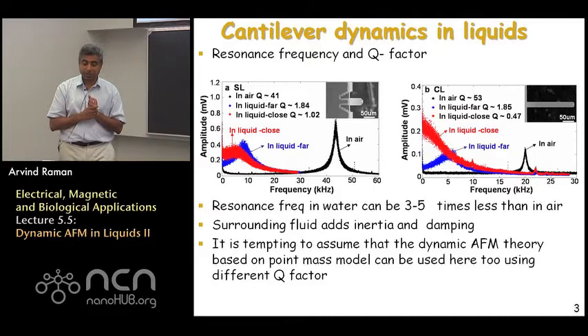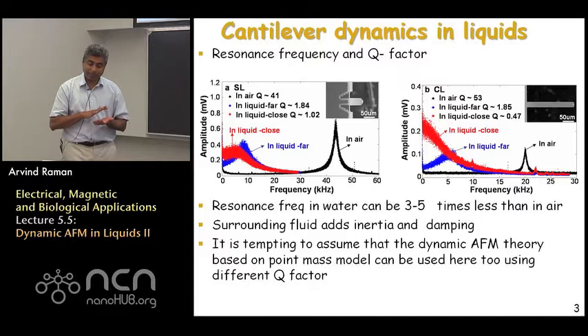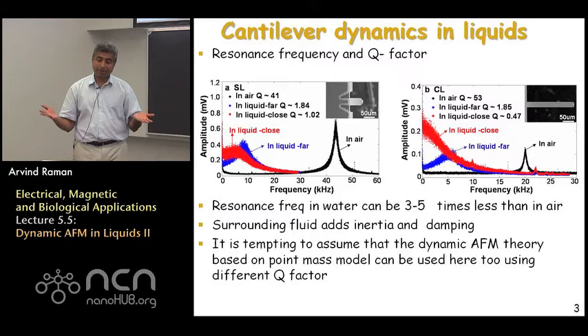On the right, similar results are shown for a conventional long cantilever where the Q in air is 53 and in liquid far from the sample is 1.85. But as you bring it really close to the sample, the resonance peak effectively vanishes — meaning the Q factor has become less than 1. So the resonance frequency decreases in water by a factor of about 3 to 5 compared to air, and the Q factor can go down by a factor of 10 to 30, depending on the cantilever.